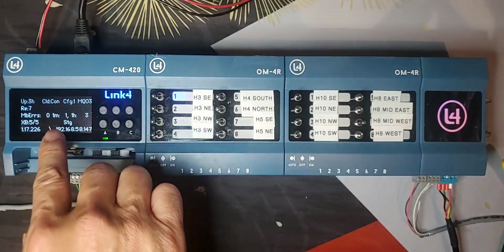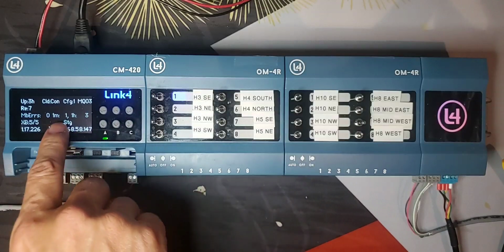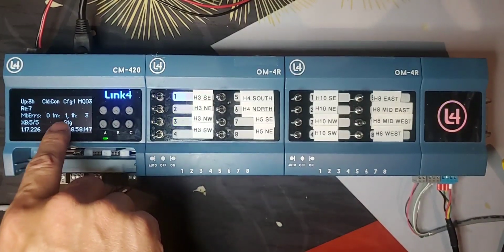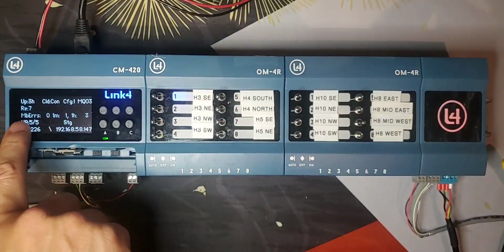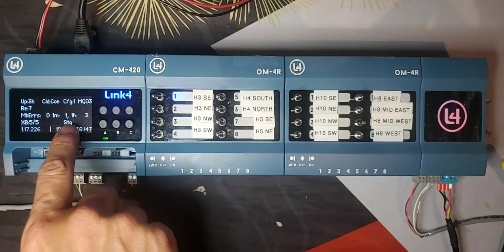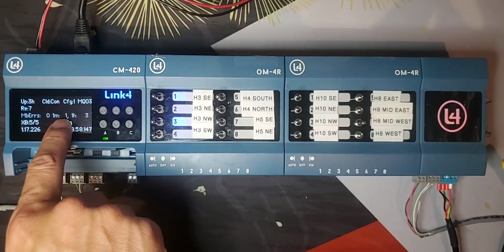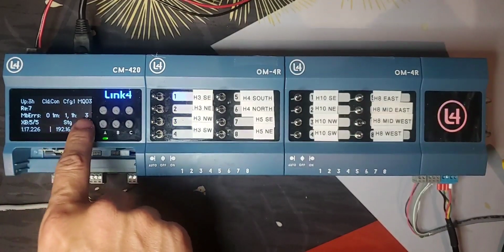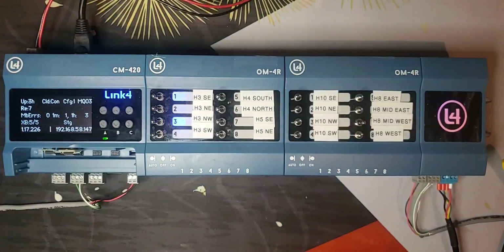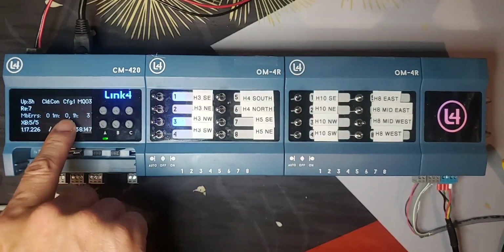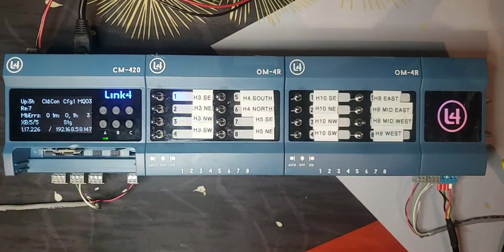So I'm going to jump into this screen to show you. You watch the beginning of the video. There was 3, and then 2, and then 1. Right. This is Modbus error. Right. So it shows how many Modbus errors it has seen in the last minute and in the last hour on average. So before I go into detail, I was going to catch it before this number goes away. You see, it went down to 0 because the time has elapsed already.